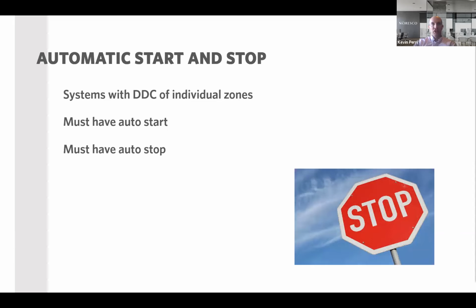Another new addition, modification, if you will, in the 2021 mechanical section. If you recall, in 2018, they had this automatic start for your mechanical systems, AKA morning warm up or morning cool down. That was introduced in 2018, that your mechanical systems need to have this auto start. Well, in 2021, they've added that it now needs to have an auto stop.